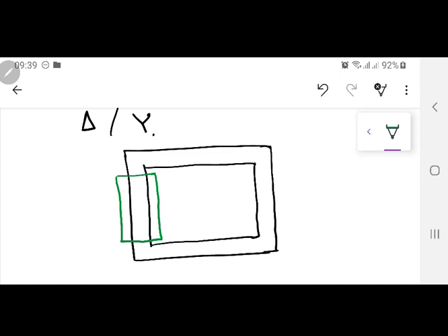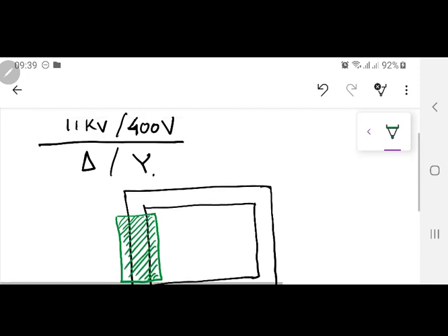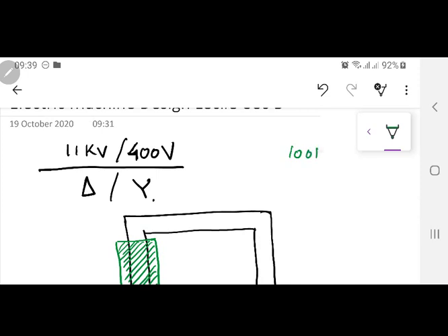So this is actually the low voltage winding. And since we all know it is low voltage winding, this means that the number of turns is small, but the cross sectional area of that conductor is very large. So overall, this low voltage winding is not just going to be one single conductor. For example, let me take one value.